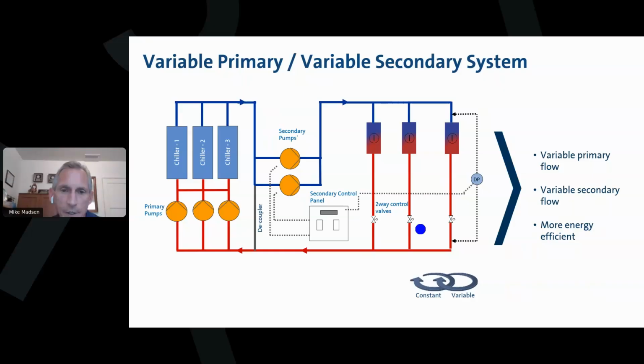And then we've got these control valves again. I talked about balancing earlier. So one of the things these control valves do, if we didn't make this closest zone the same pressure drop as the furthest zone, water takes a path of least resistance. So if we didn't balance this zone, we would get a lot more flow through this first zone and very little through the last zone. So these valves have a couple functions.